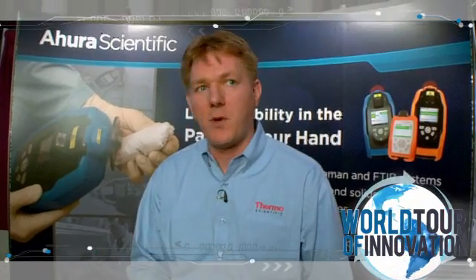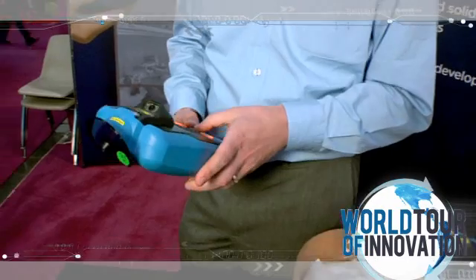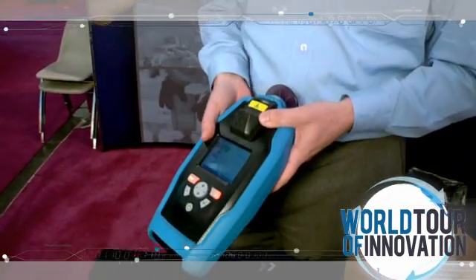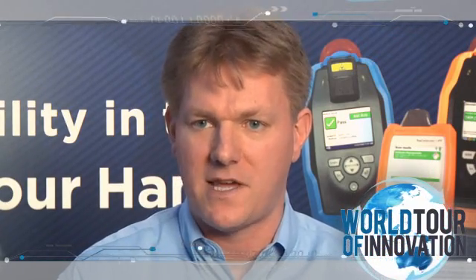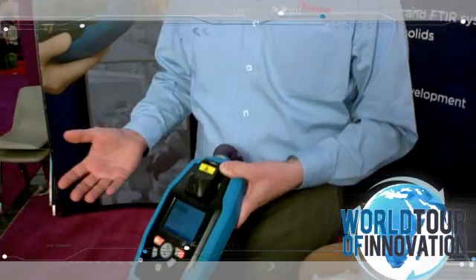What we do is first log into the device. Then what we have on the device is just a few options, so this can be used by a non-trained spectroscopist. When someone uses the device, they can either run a sample, they can do a daily performance test of the instrument, they can sync the information back to a workstation where we generate PDF, JPEG, and text reports that are secure on your server, and then under the Tools menu, we do Method and User Maintenance.